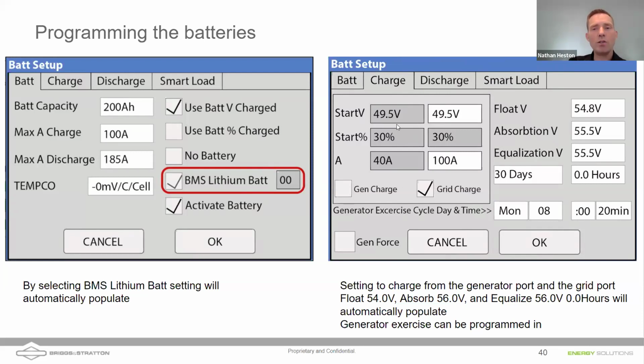If you have the gen box checked, you can change the settings here for the generator. If you don't have a generator connected, obviously you won't check this box. This grid charge box being checked allows the inverter to charge the batteries from grid once they get down to, in this case, 49.5 volts. That maximum here is the limitation. You can set a different limit for how quickly the battery is charged from grid. I could set this to 50, even though I have the maximum global charging limit set to 100. This means if the inverter is charging from the grid at 50 amps, it could also be charging from solar at another 50 amps. The float volt for all of our batteries is 54 volts. The absorption setting should be at 56 volts, and the equalized setting we do not use. You'll set that time to 0 hours.